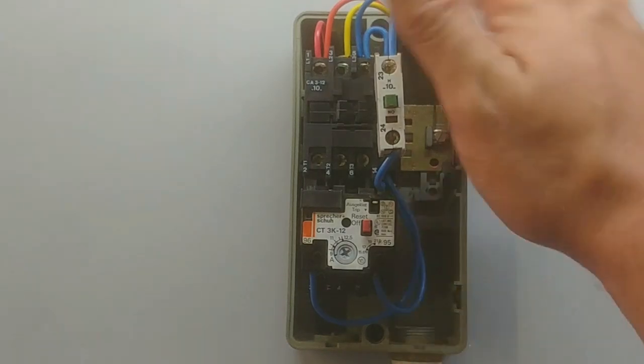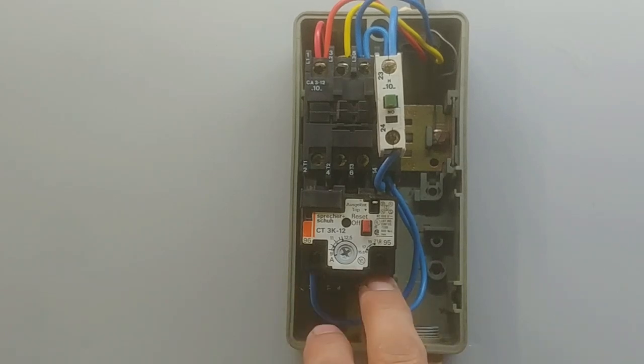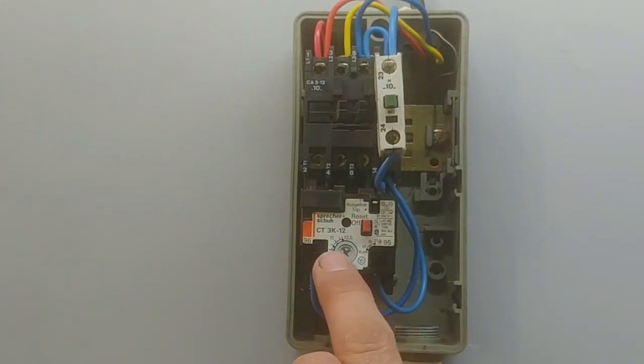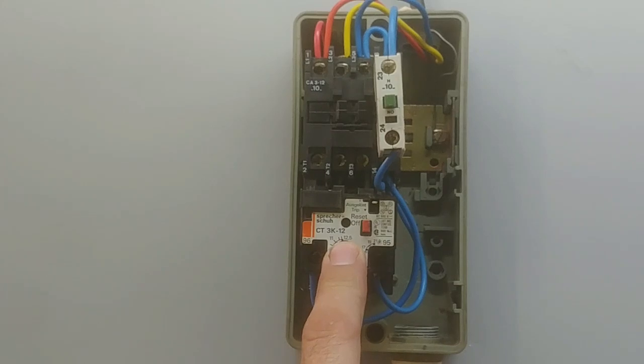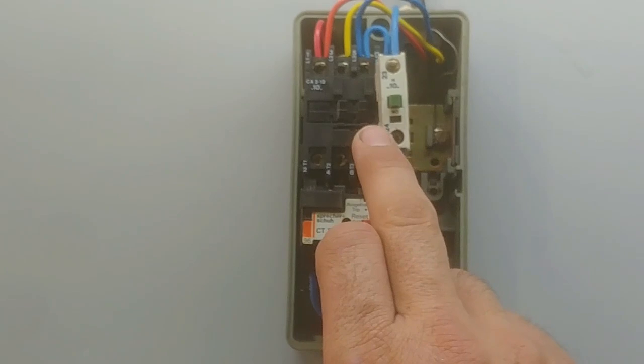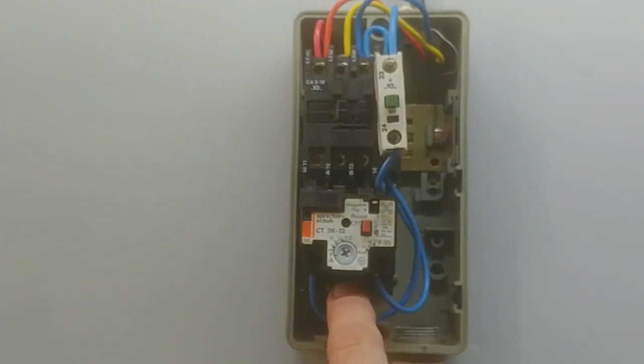Now if you connect the power, it should work. You can continue to connect the motor to the bottom terminals T1, T2, T3. If you do not put in these wires for the overload to switch off the contactor, the overload itself does not switch the power to the motor — so if you don't have these wires, the overload means nothing. You have to connect these normally closed points so that you can stop the contactor from switching on if there's a problem with the motor.